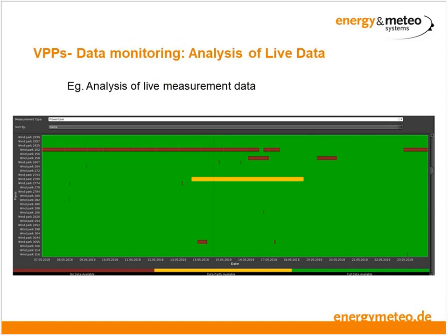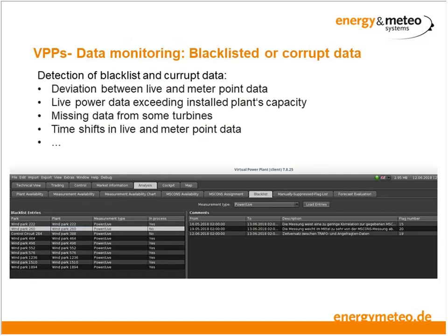You need something like a fast view for the back office of the utility, to see what to deal with. This is only if data comes or not. But often the problem is that data is corrupt. That's even more often what we see. For large wind farms that's not the big issue, but for smaller assets it's far more the case, so there's deviation between live meter data, which is from the SCADA system, and meter data.